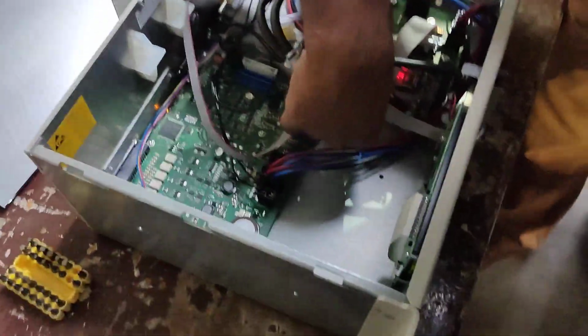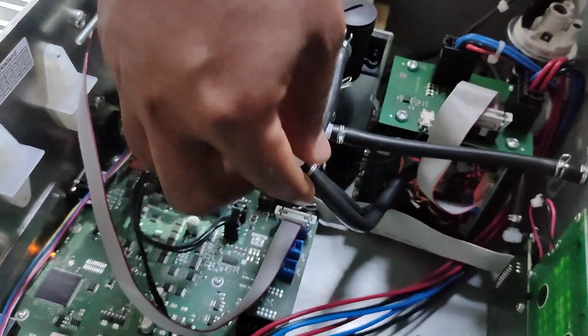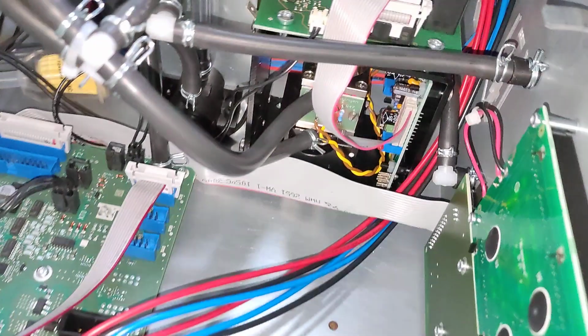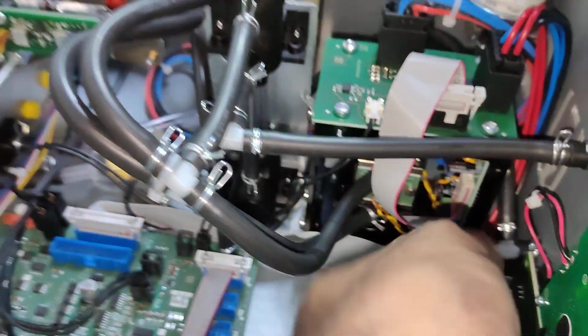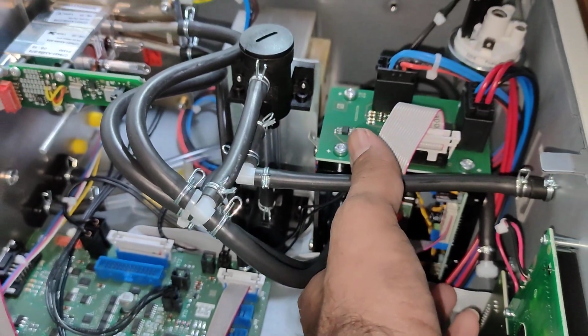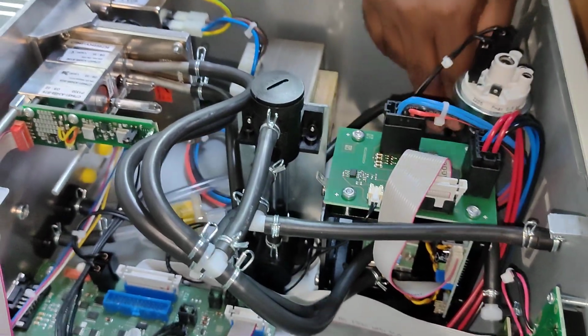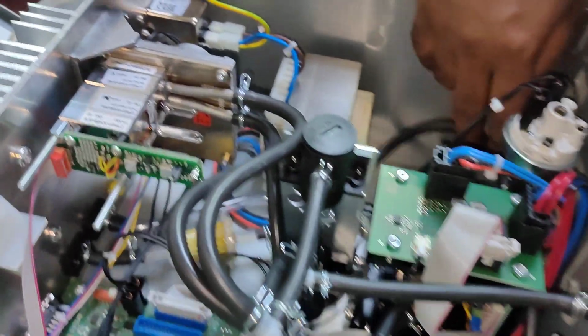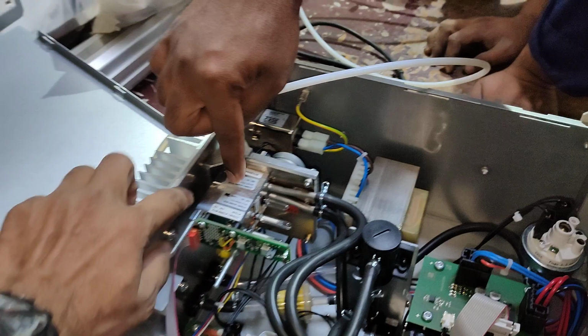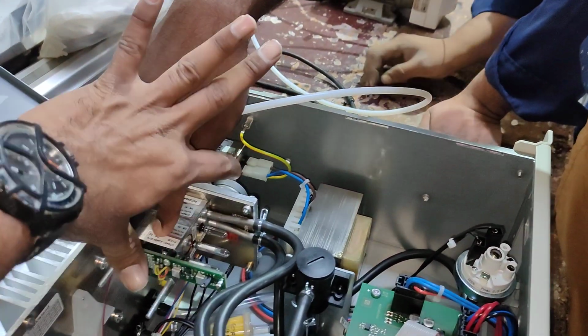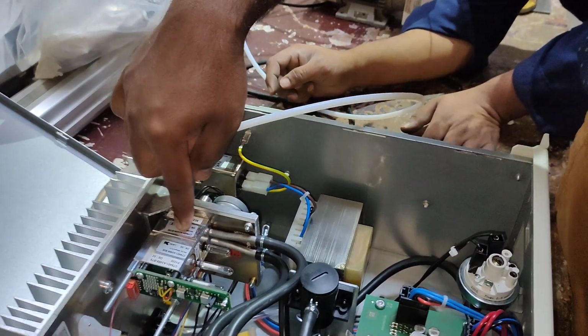Yeah, from the bottom it goes to the O2 sensor. Which one is the O2 sensor? This is the O2 sensor. Yeah, the full body is the O2 sensor. CO? CO is this one. This full pot is the detector. Yeah, this is the detector for CO. This is the filter for CO.